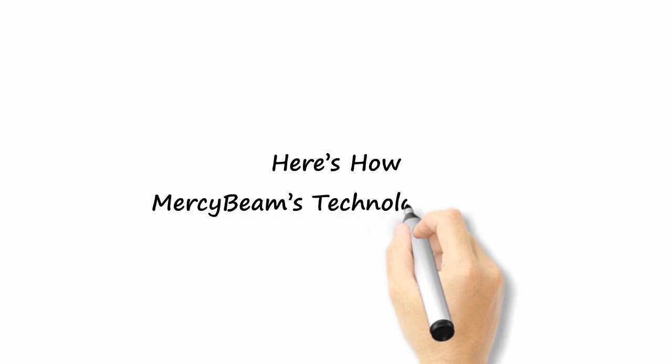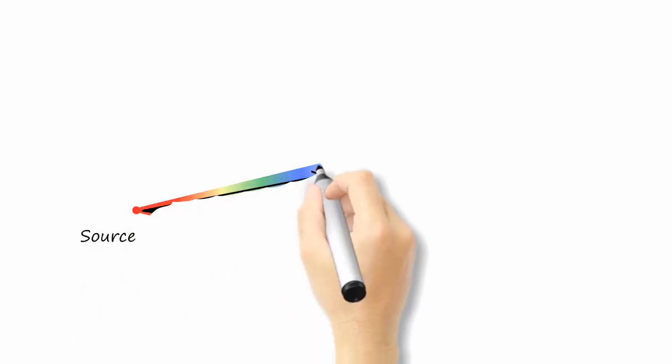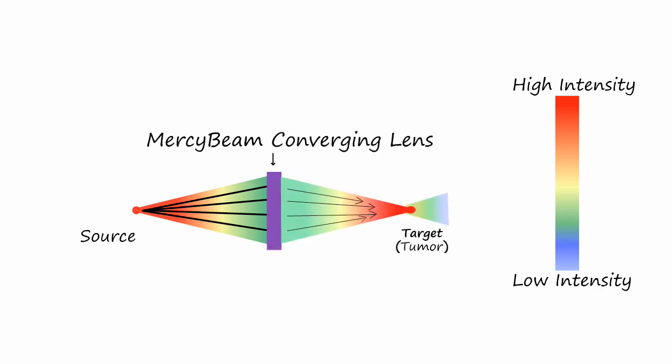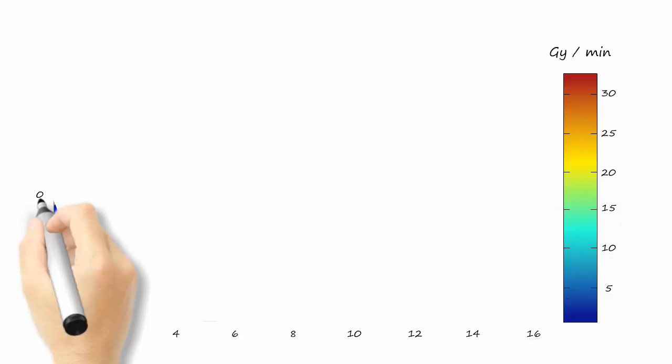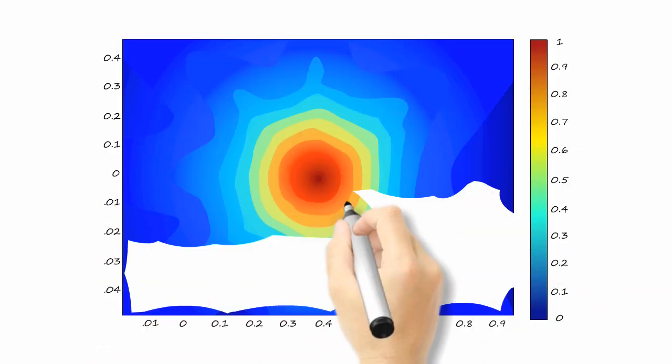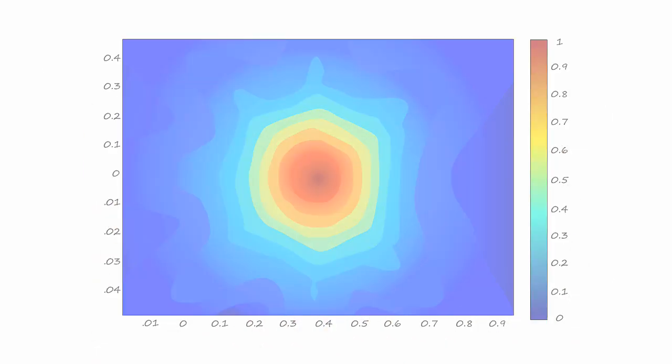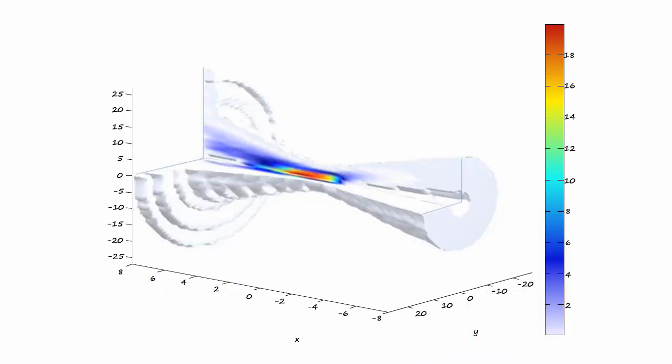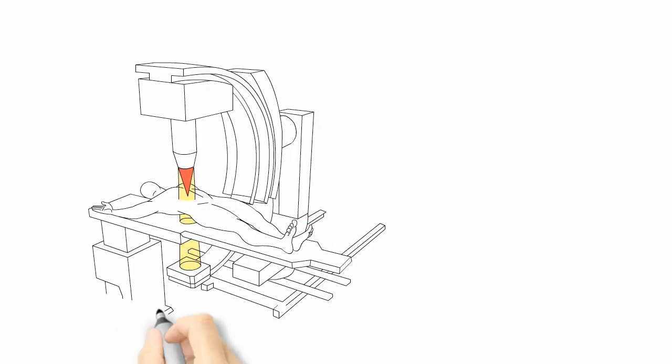Here's how MercyBeam's technology works. First, the lens collects most of the X-rays emanating divergently out of the X-ray tube and converges it toward the target location. The lens simultaneously removes low-energy photons that would be absorbed by patient skin. The convergence increases the therapeutic dose delivered at the target location, while the volume prior and after the tumor receives a very low dose or no dose at all. The cancer is treated accurately with a concentrated radiation at a fraction of the cost of all other methods.